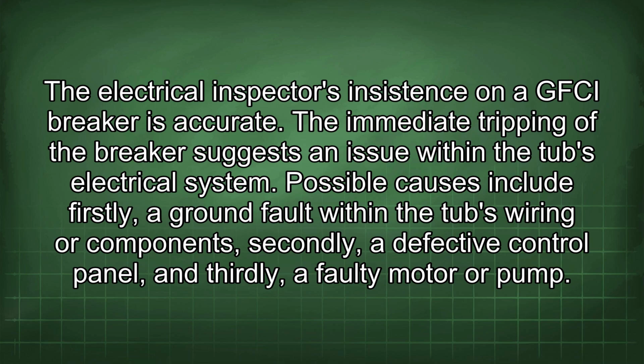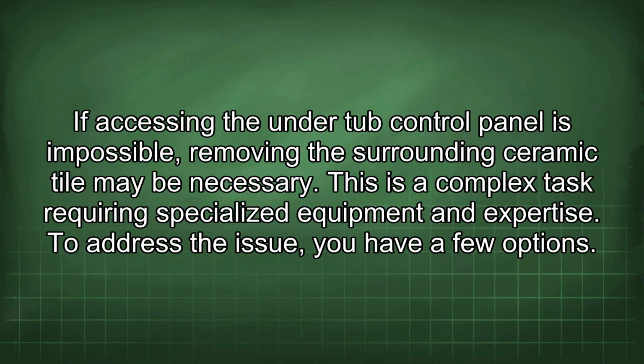The immediate tripping of the breaker suggests an issue within the tub's electrical system. Possible causes include, firstly, a ground fault within the tub's wiring or components, secondly, a defective control panel, and thirdly, a faulty motor or pump. If accessing the under-tub control panel is impossible, removing the surrounding ceramic tile may be necessary. This is a complex task requiring specialized equipment and expertise.